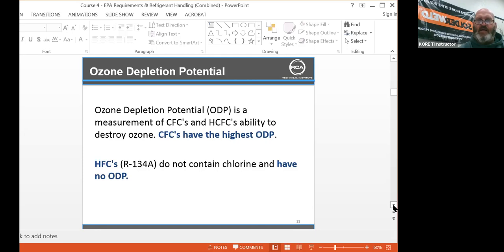and 404A is on the hit list, and probably one of the best gases still alive or around, even though it's not alive, is R12. Used R12 in air conditioning, automotive, refrigeration, medium temp. It's a fantastic gas, but it has a very high CFC count, as well as R11. If you guys have ever seen R11 in a chiller, it has a very high ODP, but we used to use it in the old days for flushing acid burnouts and washing our hands in it, washing tools in it. R11 was a fantastic gas, and that is actually the precursor where you guys ever use an R11 flush kit. That's where the R11 flush kit originally got its name, is we used to use R11, liquid R11, and flush it through the system. That's how it got its name, those R11 flush kits.